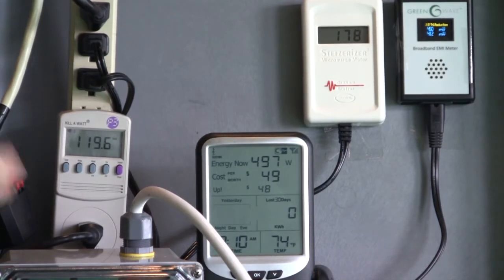Instantly, we can see the effects of a load on several meters. Number one, on our low end meter, voltage, 119.5, we're going for 120. That's actually within an acceptable amount. That will be fine for your equipment, that will be great. Next, our amps. We have a 5 amp AC Smith American air conditioner motor. It's not a particularly good motor or a bad motor. It's a 5 amp motor, and we can see here it's drawing almost exactly that, 5 amps.